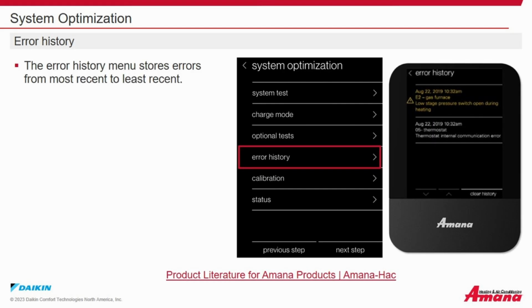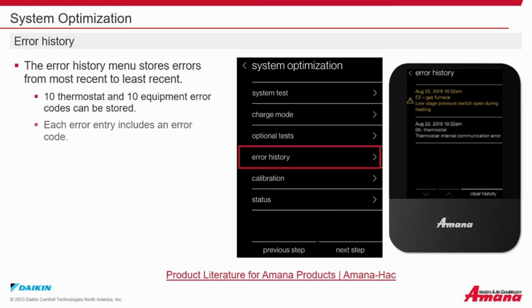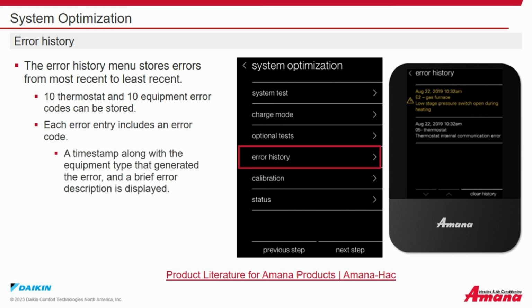System optimization. Error history. The error history menu stores errors from the most recent to the least recent. 10 thermostat and 10 equipment error codes can be stored. Each error includes an error code, a timestamp along with the equipment type that generated the error, and a brief error description is displayed.